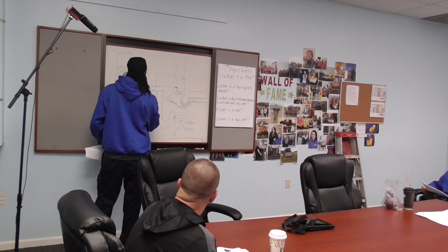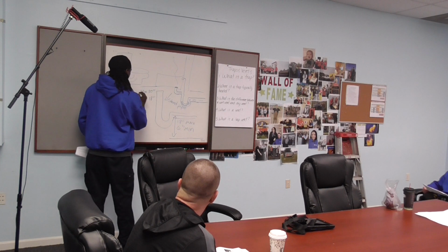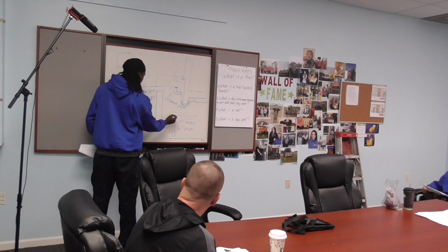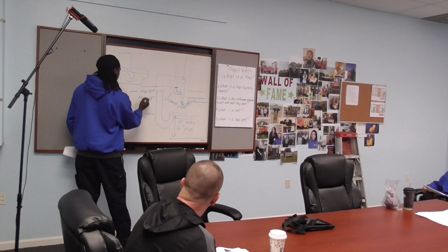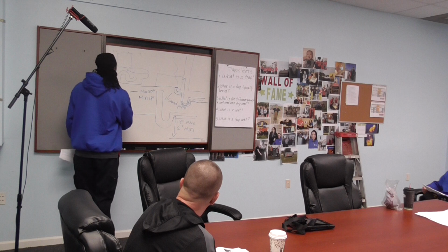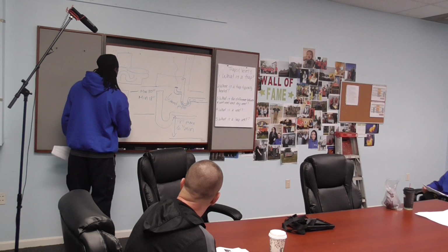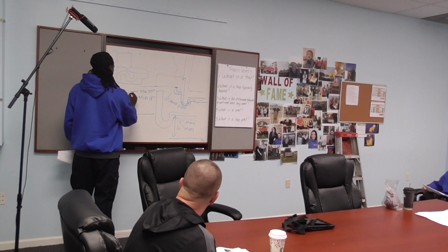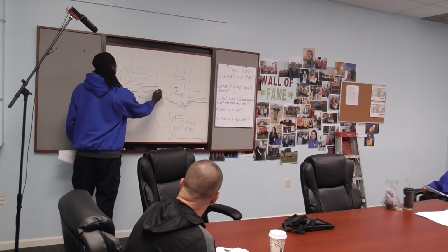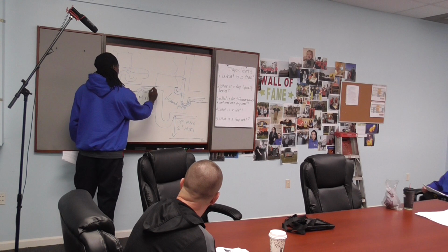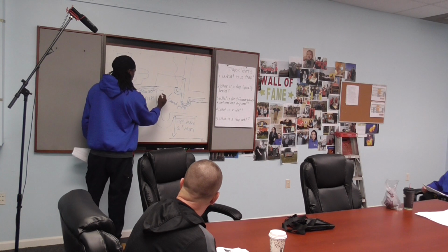And a minimum of 18 inches. So your standpipe has to be a max of 30 inches and a minimum of 18 inches from here to the top. So basically you have your washing machine here, and you'll have your drain hose going into your standpipe, and you have your water going down.